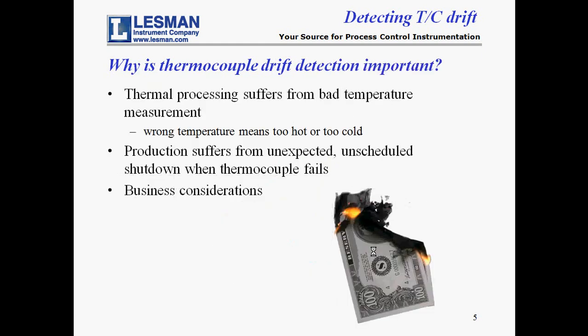Drift detection is important for two reasons. The first reason is that thermal processing suffers when the control temperature is not a true temperature. The second reason is that the chemical reactions that cause drift eventually cause the thermocouple to burn out or break. An open thermocouple shuts down the heat and brings production to a halt. Both faulty processing and halted production are important business considerations for thermal processors.